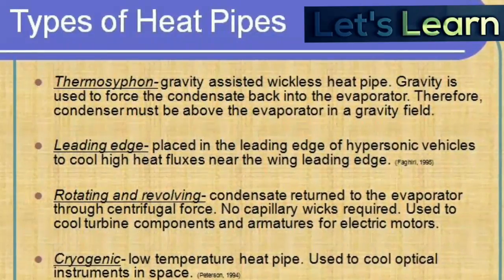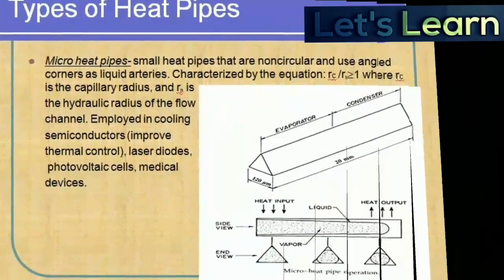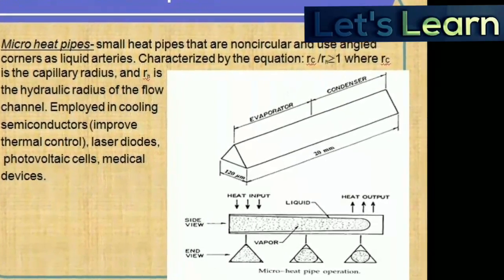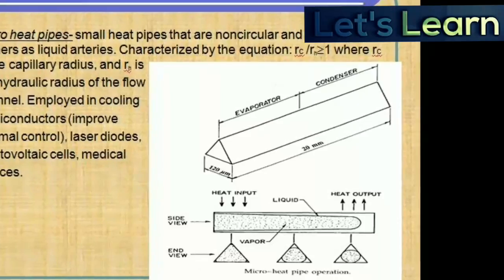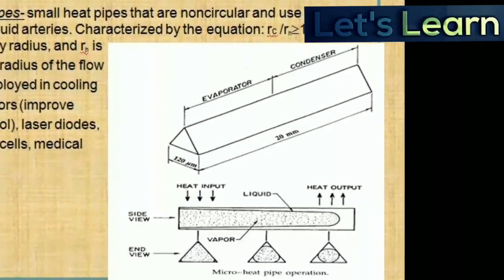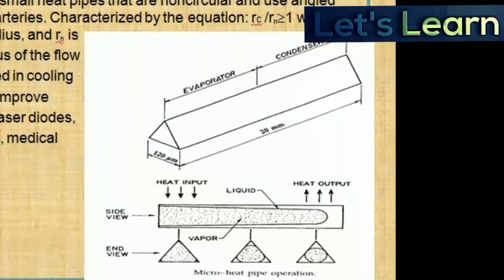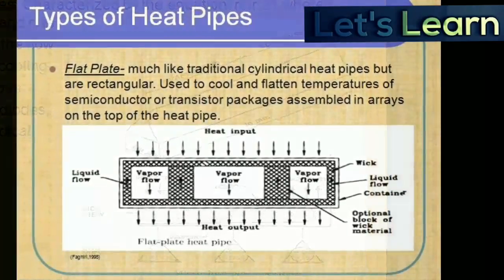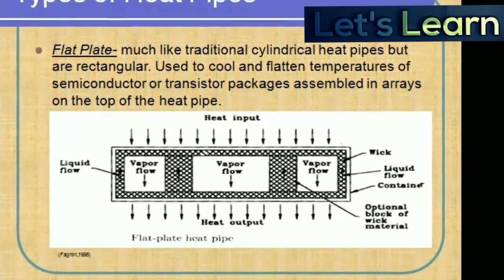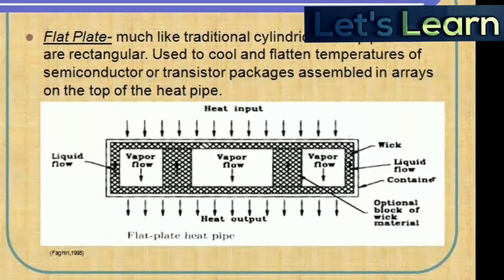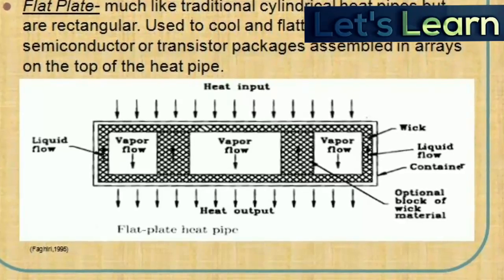The next type of heat pipe is the micro heat pipe. These are small non-circular pipes characterized by the equation RC/RH ≥ 1, where RC is the capillary radius and RH is the hydraulic radius of the flow channel. The next type is the flat plate heat pipe. These heat pipes are traditional but rectangular in shape, used to cool and flatten the temperatures of semiconductor or transistor packages, assemblies, and arrays.